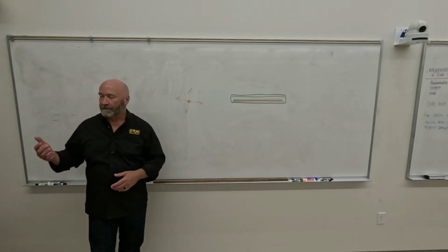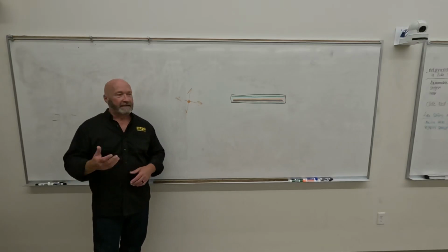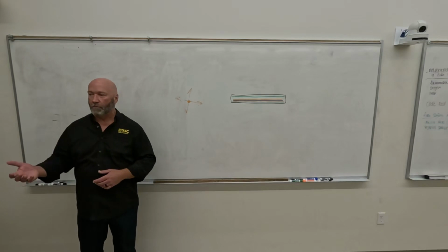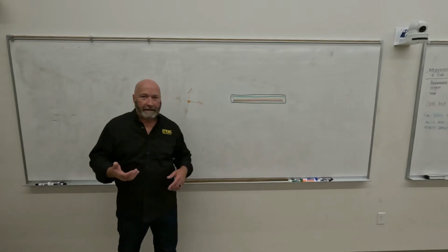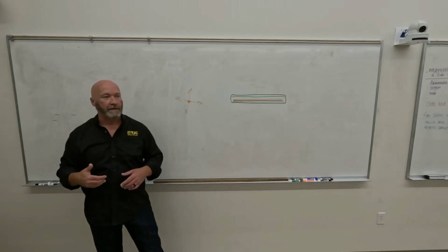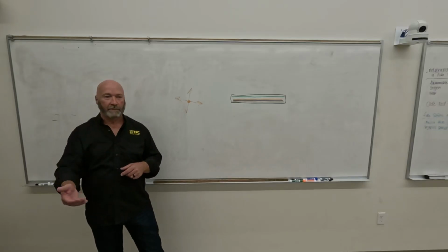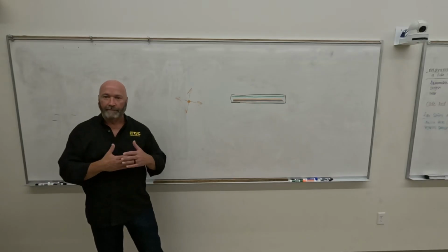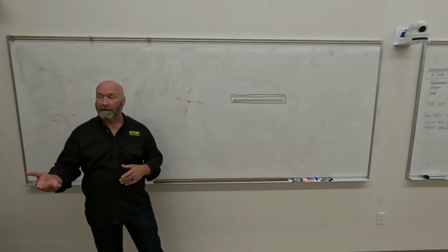How we did that was another guy came along. His name was also William, but it was Rollins. He was a dentist, so he was smart enough to know that you don't need a whole lot to get through teeth. Teeth are pretty small. So what he did was two things. One is that he wanted to eliminate those low energy x-ray photons, so he used what we refer to as filtration. Very thin sheets of aluminum just to block those low energy photons that wouldn't make it through your skin anyway. If they won't make it through your skin, they won't make it through aluminum. So that blocks those low energy photons.